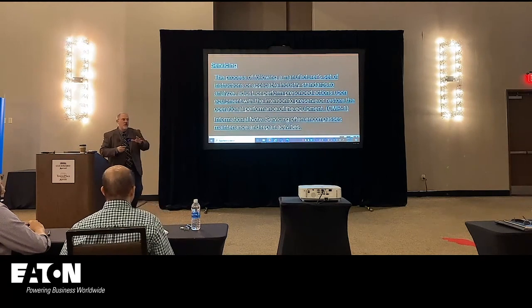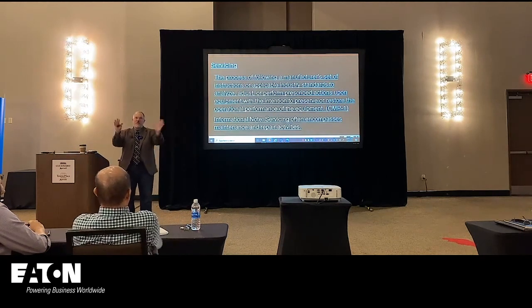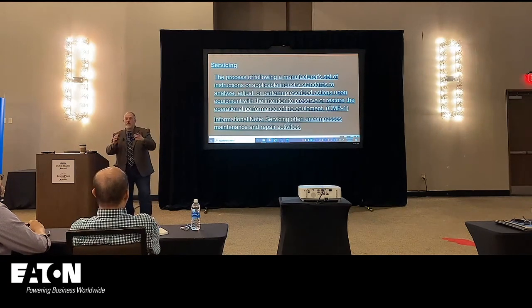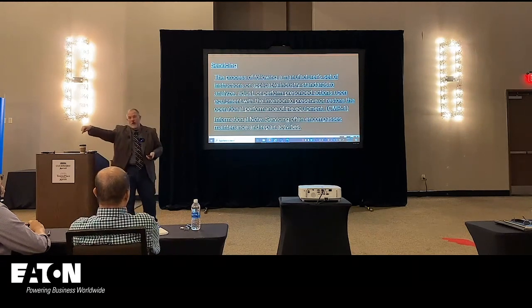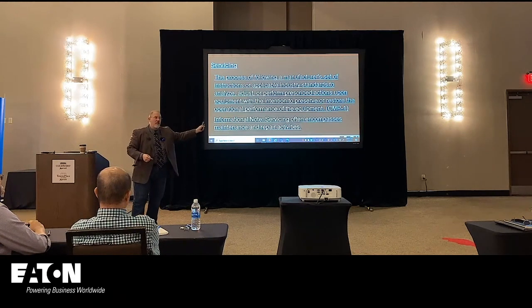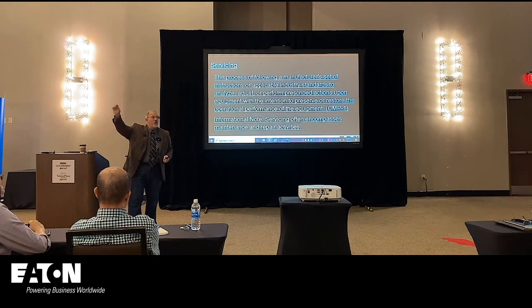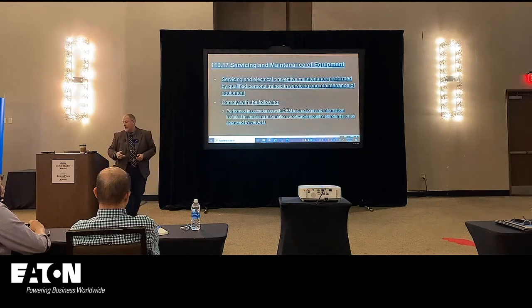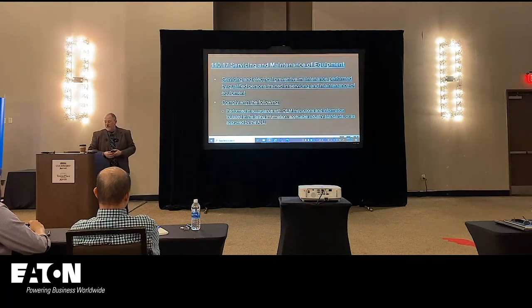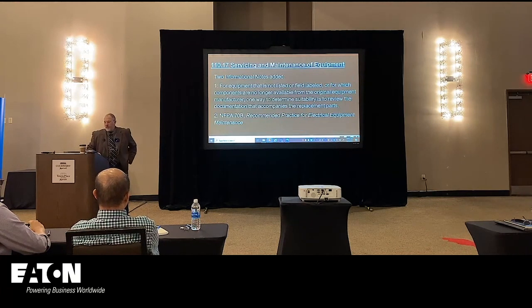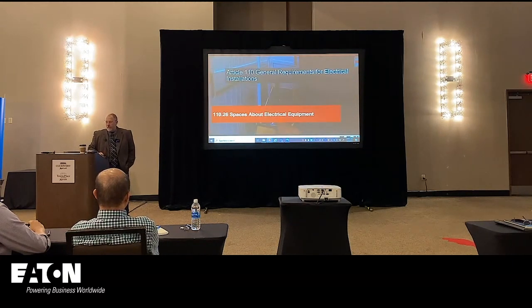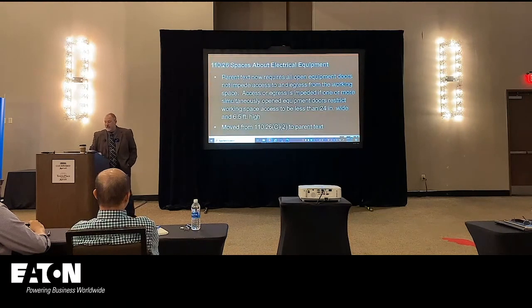This helps make sure that, if you remember, the confusion is the definitions are critical, because if I meet the definition, now I've got to follow the requirements. So because we added the definition of servicing, you should be sure that we will have requirements for servicing: where you get the parts, what are acceptable parts, and who can perform the servicing. And that's in 110.17. You can look that 110.17 up as you get through there. So we addressed servicing. This is a big one, 110.26.